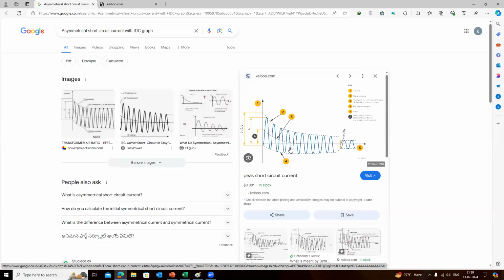By default, you might have designed your system to withstand a short circuit current, not for an infinite time, but for a specific time. For example, transformers withstand the through fault current for 2 seconds. Switchgear, 1 second. Cables, 2 seconds or 3 seconds or 1 second, something like that. Even if you protect the cable by a fuse, it may be the fuse operating time or the let-through current. If it is a breaker, 0.12 or 0.15 seconds, something like that. It depends upon the sizing criteria that you have selected.